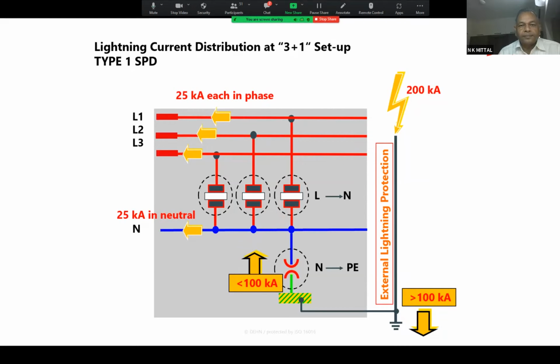Yeah. Now we go for this 25 kiloampere and 100 kiloampere. Yes. So you see here basically, let us say total lightning is 200 kiloampere. It will depend. It can be 200, it can be 50, it can be 150. Depends upon the area and geography and all other things. Just for example, if it is 200 kiloampere, which is the worst case actually, the peak value of type 1 SPD is there. So then in that case, you have earth resistance. Let us say, or forget about even the earth resistance now. There is a 50-50 rule.